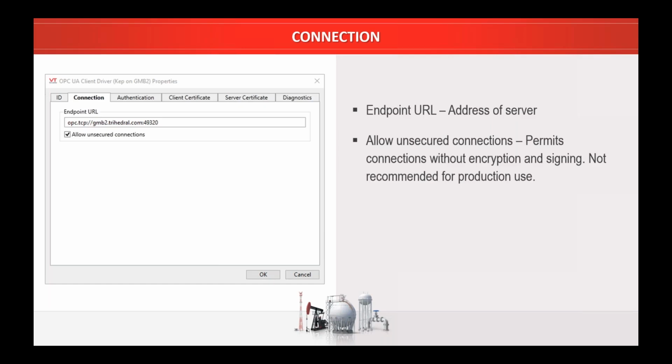The server certificate identifies that server machine, and the name has to match the name that you put in the URL here. And then you can have an optional port at the end of the URL, the colon, in this case, :49320. The OPC server that I'm testing with runs on that port. There is a standard port for OPC-UA, which for the life of me I can't remember, so you wouldn't need to provide it if it was running on the standard port, but apart from that, you can just explicitly put the port there.